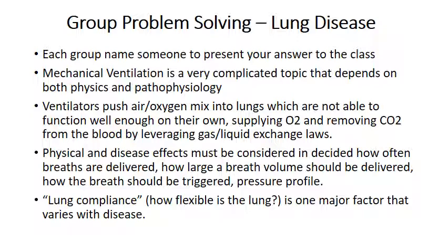But ventilators in general push air-oxygen mix into lungs, which are not able to function well enough on their own, supplying oxygen and removing carbon dioxide from the blood by leveraging the gas-liquid exchange laws. Physical and disease effects must be considered in deciding how to set up how often the breaths are delivered, how large a breath volume should be delivered, how the breath should be triggered, pressure profile, alarms, other concerns.